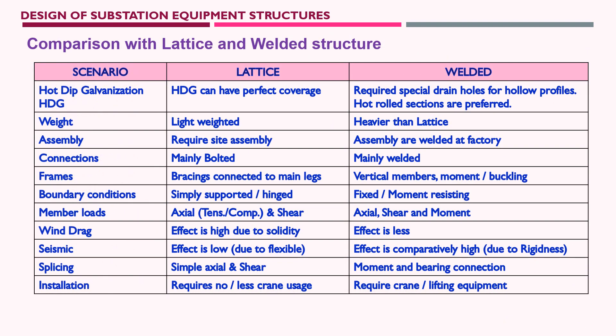Next, we compare lattice and welded structures. Looking at a comparison table with three columns — scenario, lattice type, and welded type. For hot-dip galvanization: in lattice structures, hot-dip galvanization provides perfect coverage of the entire structural surface. For welded structures using hollow profiles such as circular hollow, square hollow, or rectangular hollow, holes must be provided to drain the galvanization liquid — at the bottom, top mounting plate, or in the sides of the hollow profiles.